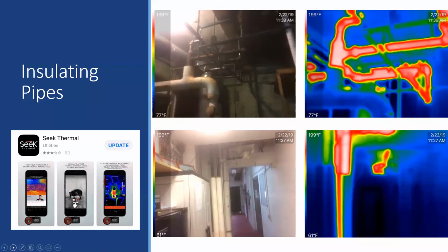Pipe insulation is a low-cost opportunity, and for this facility, it would have a payback of 6 months. Also know that the pipes are hot and very dangerous for people to accidentally touch. These are all within the realm of someone leaning against. So just keep in mind that this type of heat is not only dangerous for a person, but will degrade your building. As it lays in between the walls and has no insulation around it, it will definitely degrade the concrete walls or insulation that you have around it. Keep in mind.